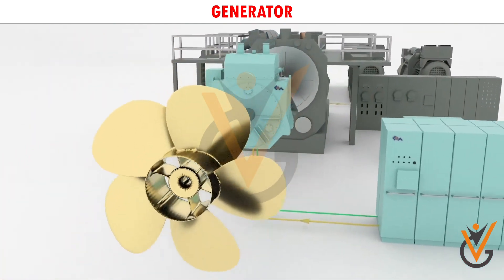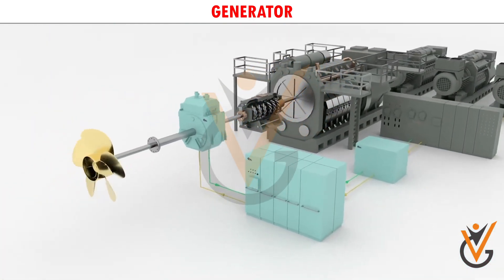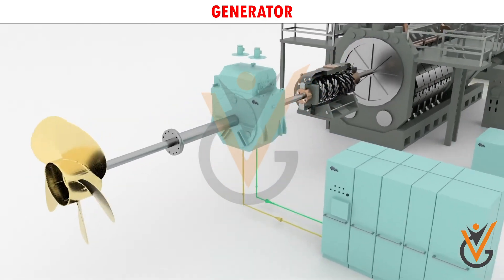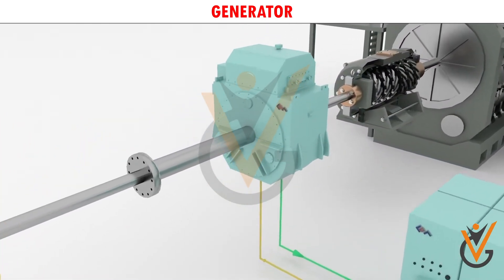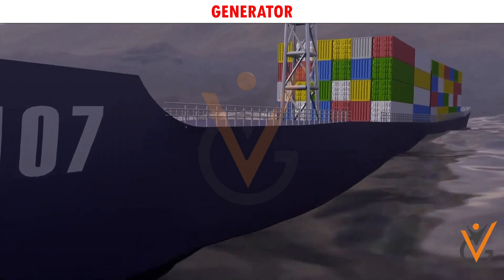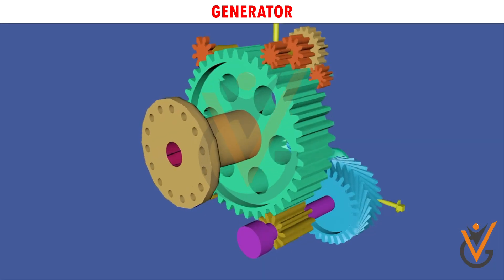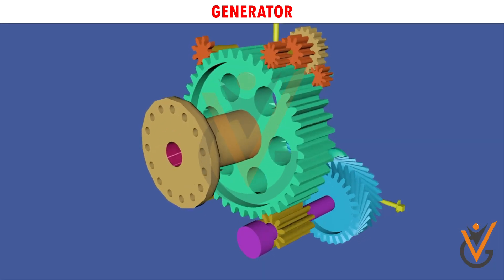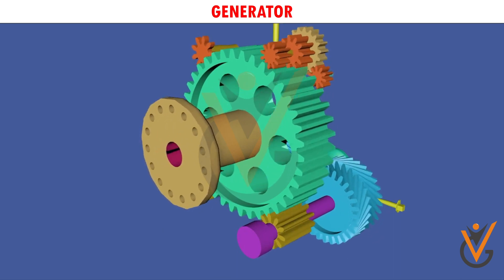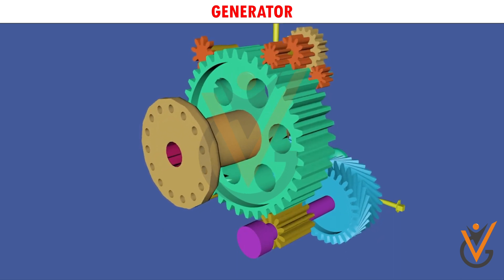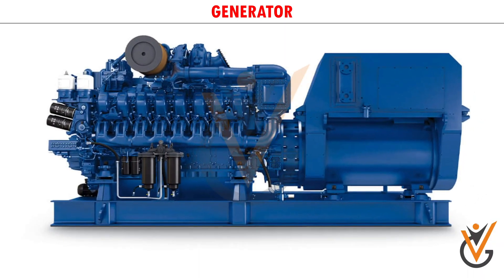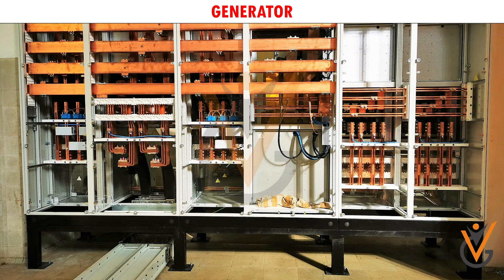Many ships are equipped with shaft generators, where the rotation of the main engine of the ship is used to operate the alternator and generate additional electricity. As main engine speed varies per the requirement of the ship, a gearbox arrangement is provided to supply a constant speed to the shaft alternator. The power generated by these marine generators is transported to the main switchboard using a busbar.